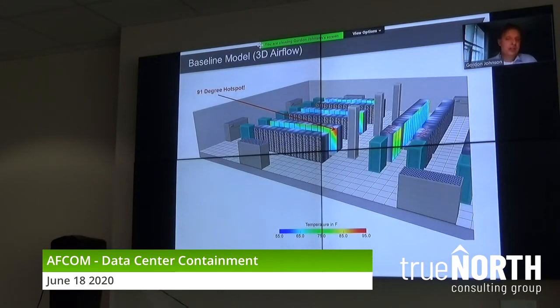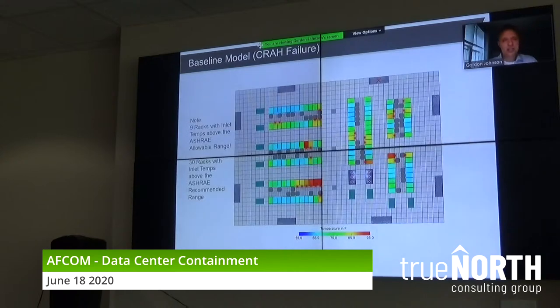Here's the delta T that I spoke about early on. I mentioned I want a 1, 2, maybe a 3 degree delta. I don't want a 29 degree delta. Look at the bottom of that rack with the red arrow. 62 at the bottom from the perf, in the middle of the rack, mid 70s, at the top of the rack, 91 degrees. Again, I cannot do any cooling optimization in this data center.